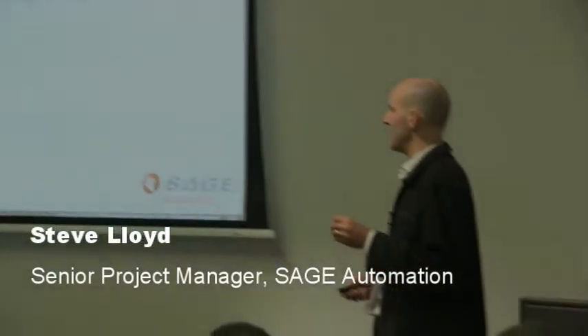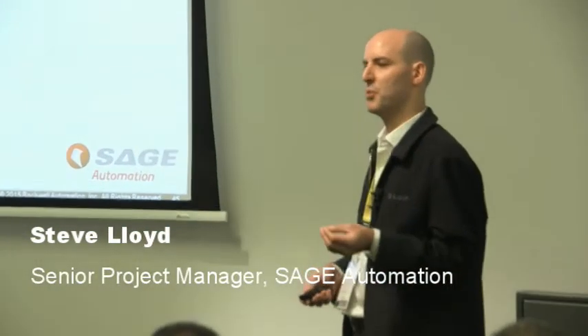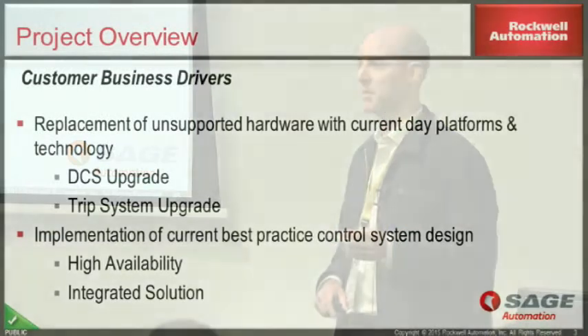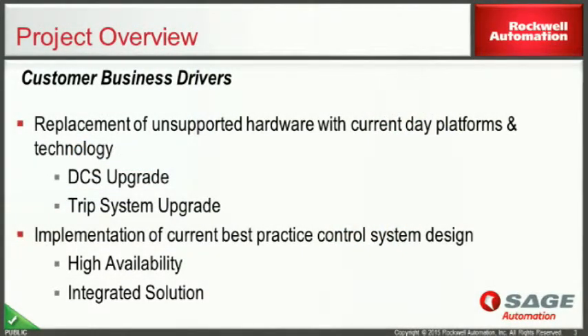Upgrades. The main driver was unsupported and obsolete hardware. The DCS that was in use was a Toshiba Tosdic DCS, 1970s, 1980s type technology, and they were running out of spares essentially on site.